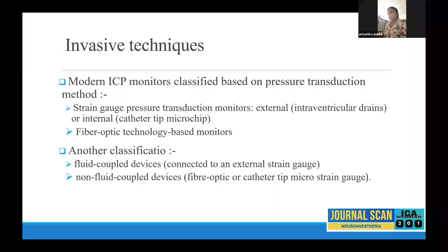The second commonly used technique is fiber optic technology. In fiber optic, light is transmitted and reflected back, and the change in the reflection is amplified and recorded as a pressure change. Others are fluid coupled devices, the same as how we monitor arterial line pressure. And there are non-fluid coupled devices, also based on fiber optic or catheter. That is another way of classifying. Fluid coupled means they are hollow. Non-fluid coupled means they are not hollow, so no fluid is connected between the brain and the outer system.